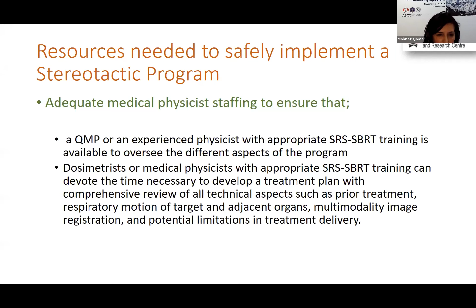In addition to, obviously, trained experts, you need some equipment or instrumentation to actually be able to validate the whole system. One of the most common ones is the radiation detectors, since everyone knows we're dealing with very small field sizes and very small apertures. So the regular detectors that we often use in clinic are not suitable. In order to commission the system for adequately measuring small fields and apertures, whether it's MLCs or cones, we need really suitable micro detectors, and also reference grade electrometers, which are able to detect the really small signals from these very small apertures.